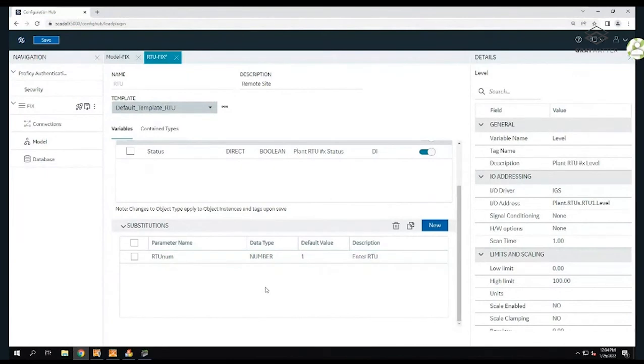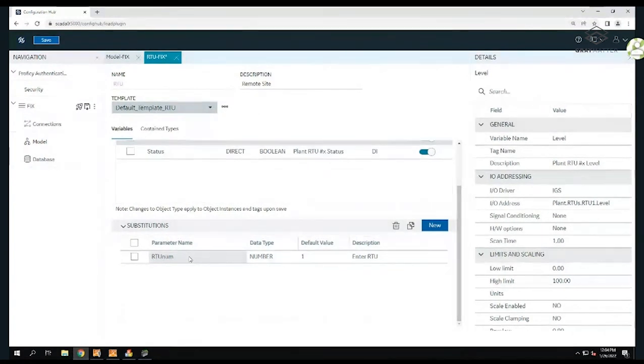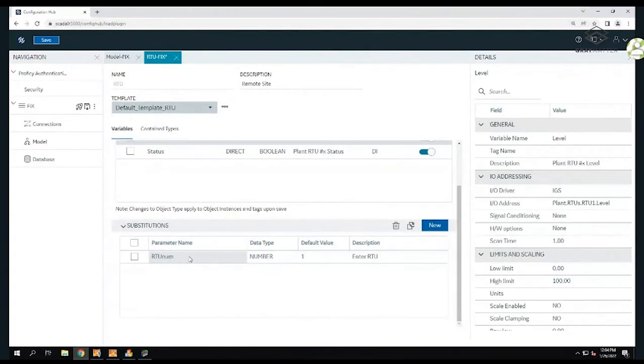A couple of audience questions: Is there a limit to how many tags you can publish at one time without stopping SAC? I don't have firsthand experience with that yet since we're pretty new with the release. I'm told it's magnitudes quicker when you stop SAC. If you're developing offline on a new system that's not running actual processes, I would probably stop SAC and get it done. If you're in a live system running product, you really don't want to do that.